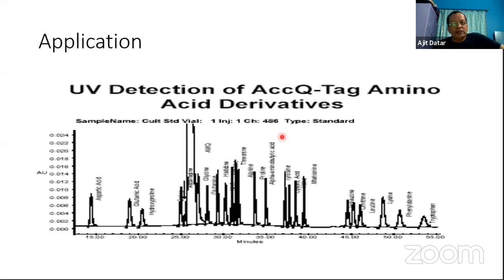The modification to it is called a PDA detector, photodiode array detector. The principle is the same. We use the same deuterium or tungsten lamp. The only difference is that we get a spectrum instantaneously because I'm using several detectors here, a 512-element photodiode array. So for each individual wavelength, there is a detector. When the grating disperses the polychromatic radiation, individual wavelengths fall on these detectors, and you get a simultaneous spectrum as well as chromatogram.